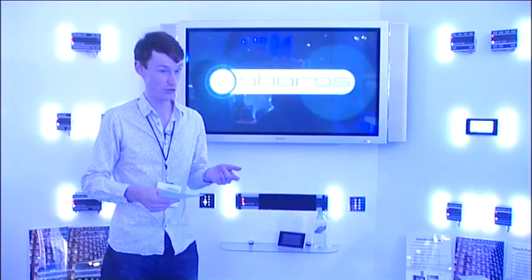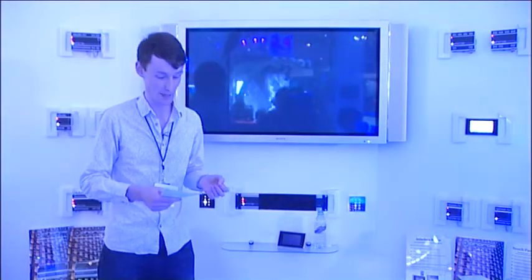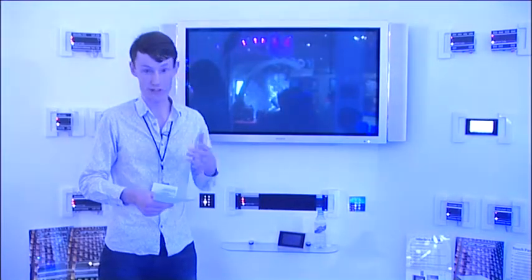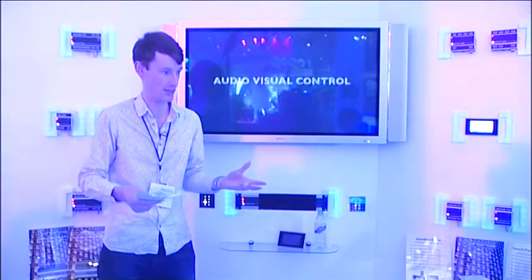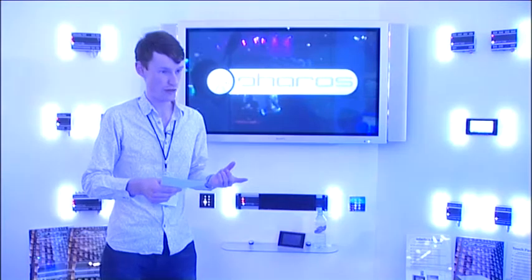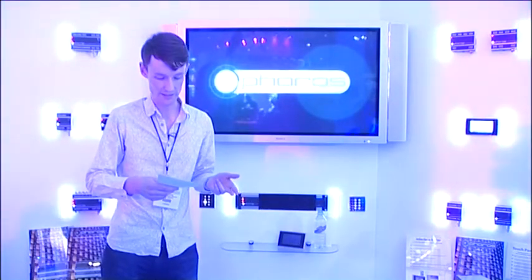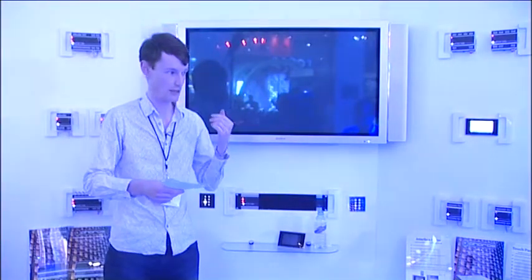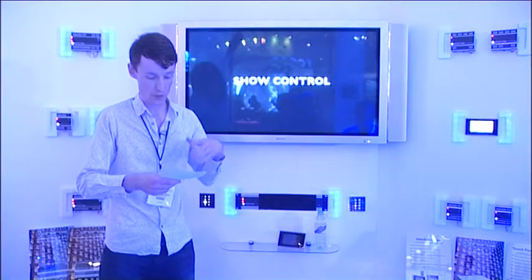The operation mode, master or slave, is configured in software, along with group setup, scene setup, timeline programming and the patch, and also interrogating the ballasts over the bus, a bit like RDM, to find out what's out there and what the addresses are. So that's 6,400 ballasts, one centralized control system working over Ethernet, timeline programming, plus the conditional logic system that we've had in our controllers for years, but applied to DALI.